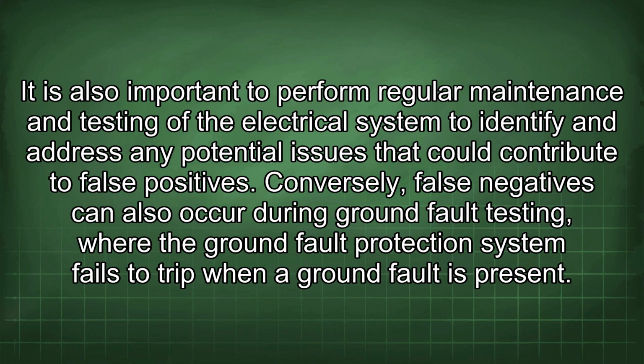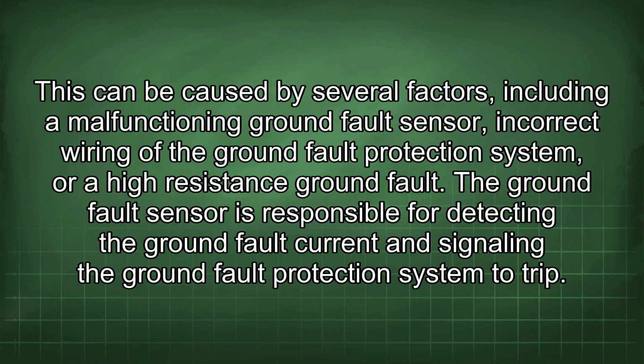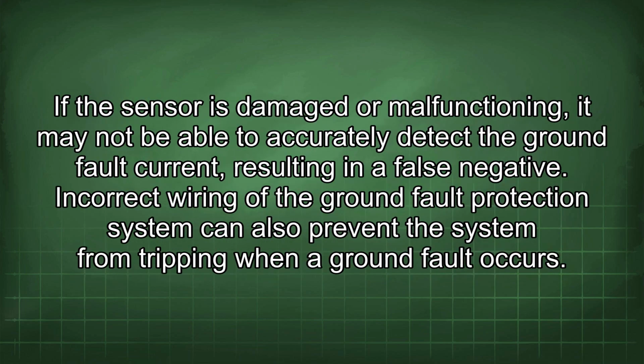Conversely, false negatives can also occur during ground fault testing, where the ground fault protection system fails to trip when a ground fault is present. This can be caused by several factors, including a malfunctioning ground fault sensor, incorrect wiring of the ground fault protection system, or a high resistance ground fault. The ground fault sensor is responsible for detecting the ground fault current and signaling the ground fault protection system to trip. If the sensor is damaged or malfunctioning, it may not be able to accurately detect the ground fault current, resulting in a false negative.